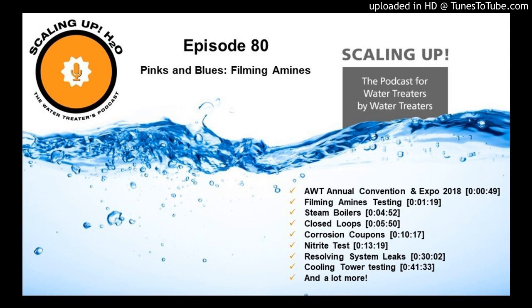So after we ran all of our tests, some like we would normally run on a closed loop, but then we also ran the Filming Amine test, and we got absolutely no Filming Amine in the system. We then added an additional 750 parts per million of Filming Amine to the system, so that gave us a total of 1,500 parts per million of our Filming Amine product. Two weeks later, we came back and the water was even darker. And we did have a positive for the Filming Amine test.